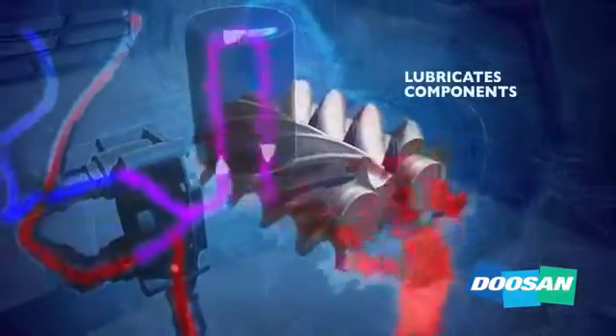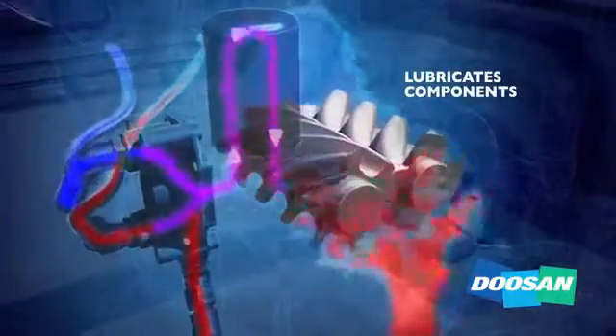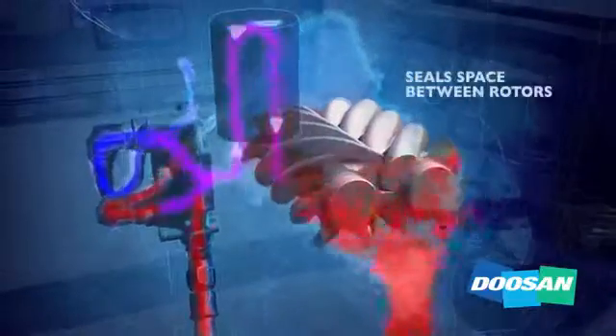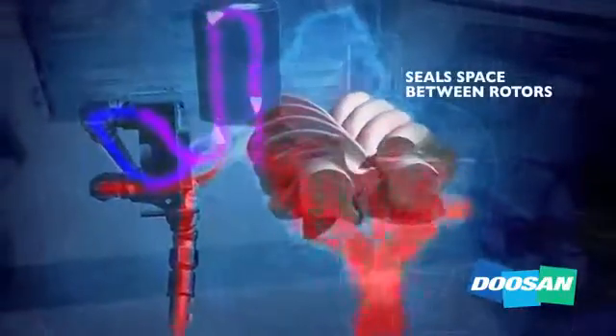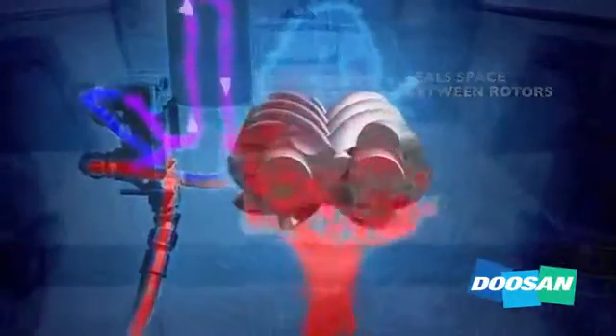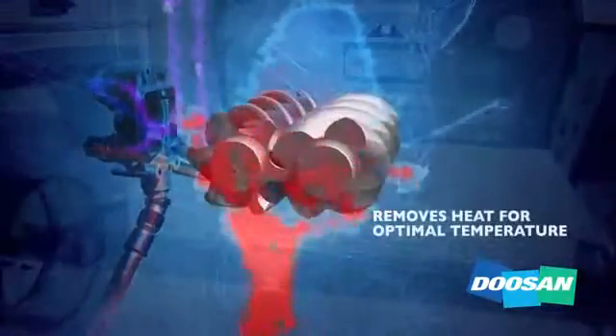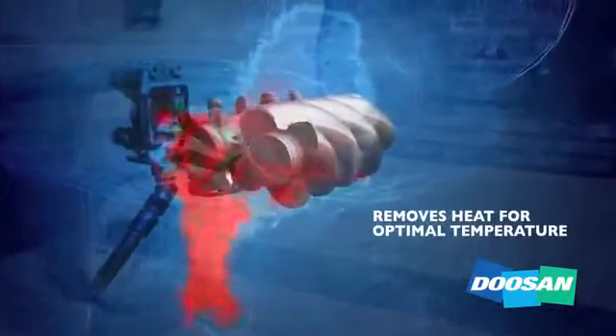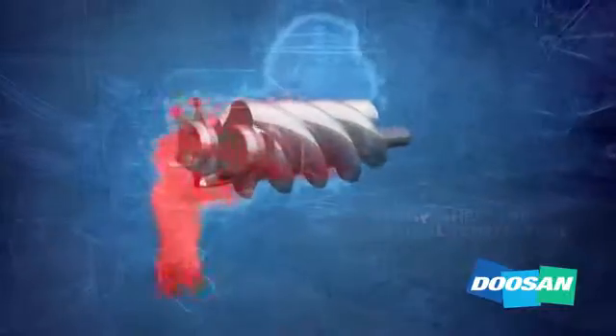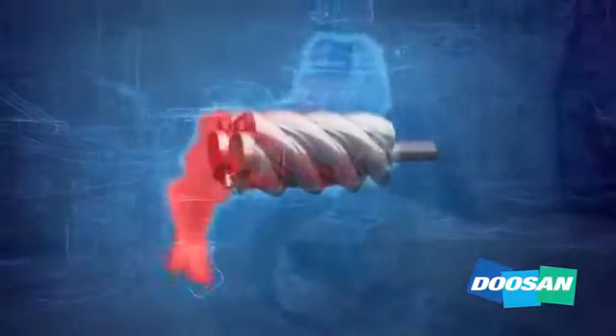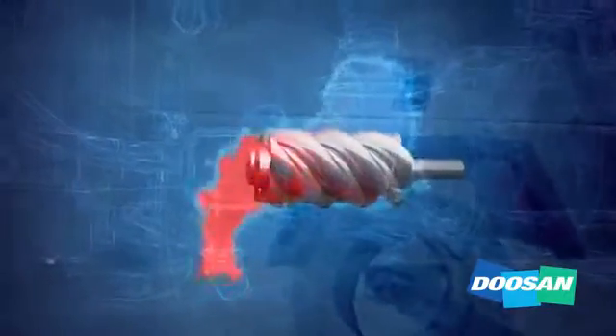1. To lubricate the rotors, bearings, and seals. 2. Seal the space between rotors to keep pressurized air from escaping back to the inlet. And 3. Remove heat from the system so the air end can run at optimal temperatures. Using oil to maintain proper temperatures maximizes efficiency of the compression cycle.